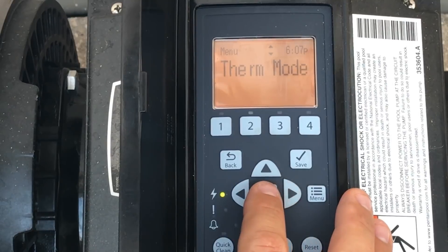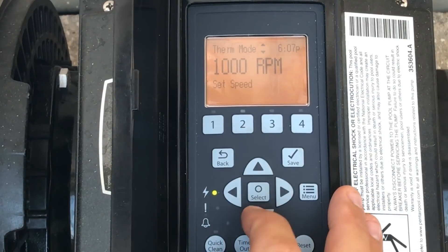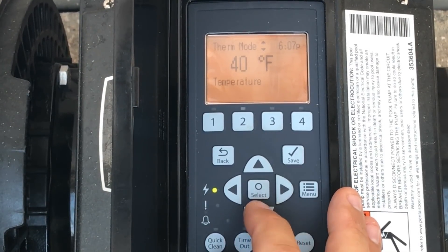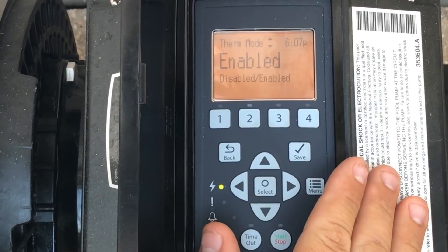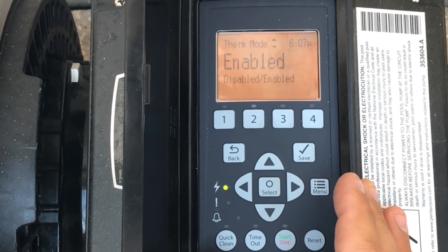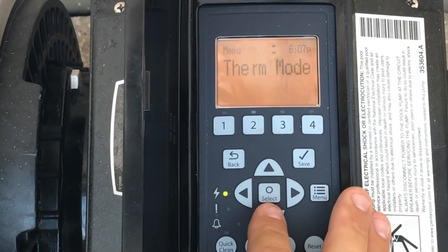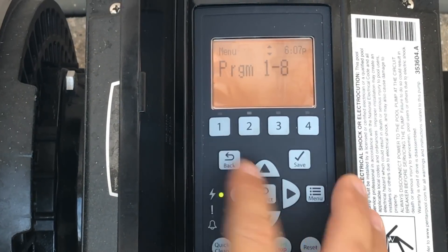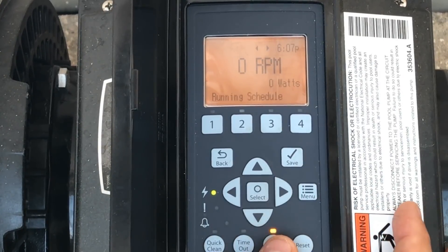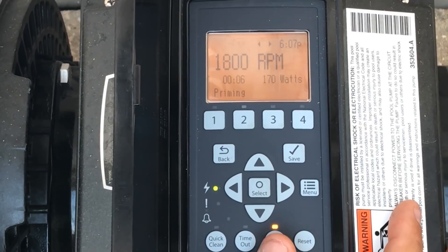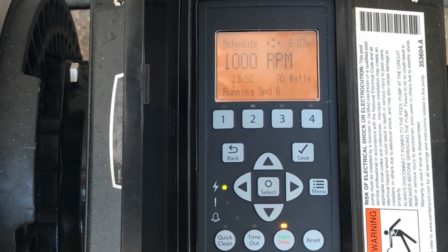Thermal mode is important for people in colder regions. Enable it, set the speed type to speed at 1000 RPMs, and set it for 40 degrees. What thermal mode does is protect the pipes from freezing — once the pump recognizes the water temperature is 40°F or below, it runs at 1000 RPMs to raise it above that temperature. That's how you program the pump. Bring it back to the main screen, hit start/stop, and it'll prime up and run to whatever speed it's programmed for. Hopefully this helps — don't forget to like and subscribe!